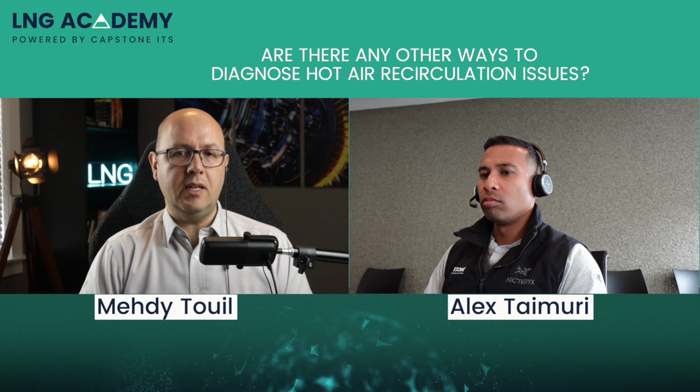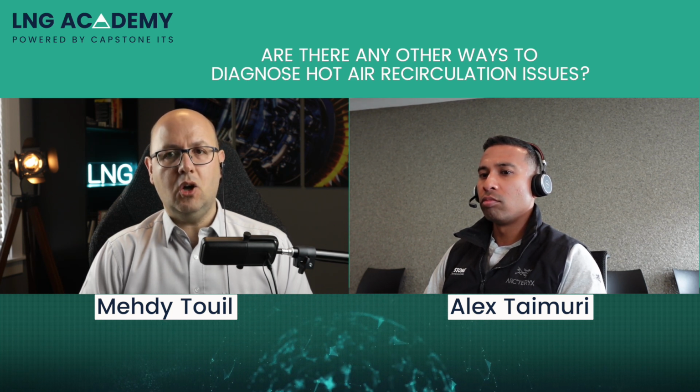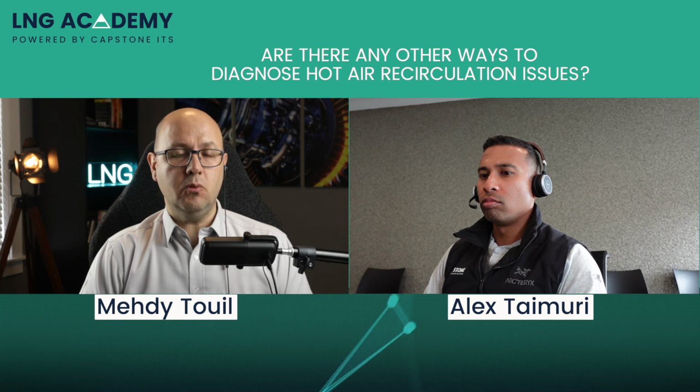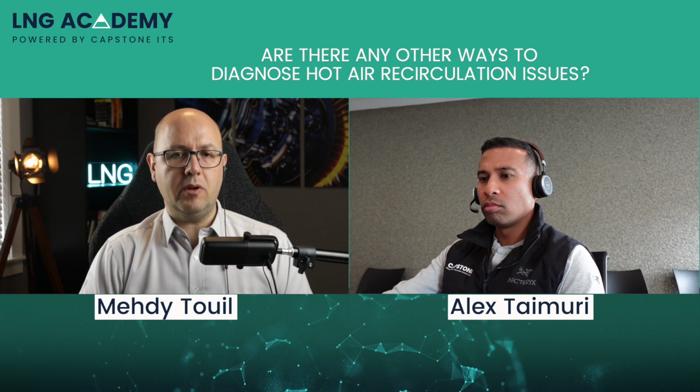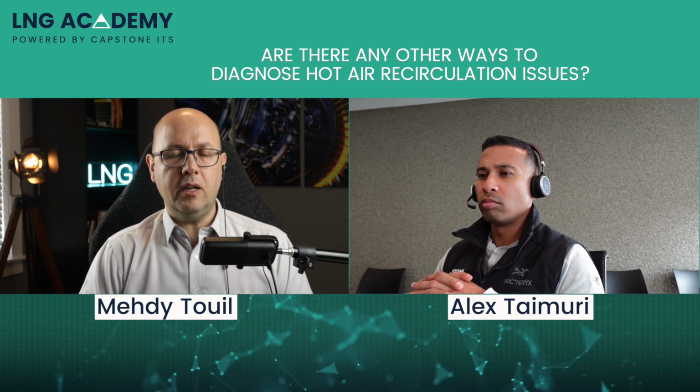To minimize hotspots, it is also possible to enhance circulation by adding or removing structures from the facility whenever possible, of course. And beyond the analysis of weather, CFD data, and cooler performance, establishing a diagnosis for an existing facility is a complex exercise that involves the installation of dozens of temperature sensors at the cooler's intakes in an evenly distributed fashion to visualize the phenomenon throughout the day.